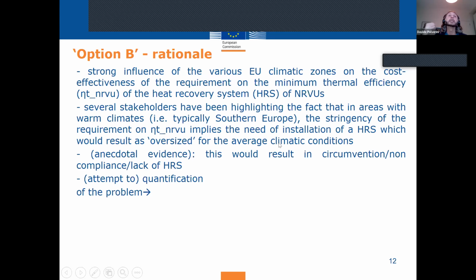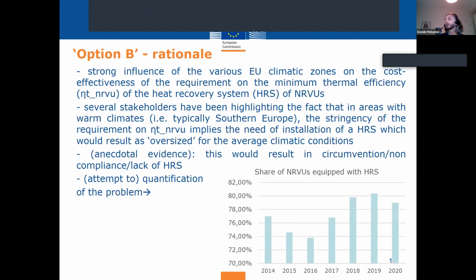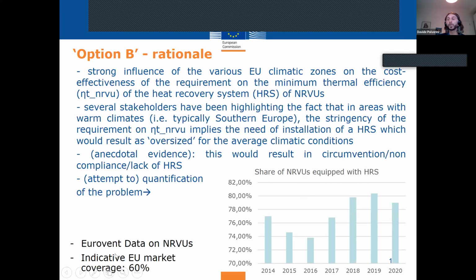So basically, it would seem that systems, ventilation units are still placed, in particular in warmer areas, without the properly due heat recovery system. We made an attempt to quantify the problem, even if obviously it's not easy because it's a matter to get evidences about non-compliances. We based on some data of an association of the sector, Eurovent, that issued some data related to the number of units. This is split throughout the whole European market, so there is not the relevance or the predominance of any specific region. And this graph here shows year by year the estimated percentage, the estimated share of ventilation units which are equipped with a heat recovery system.